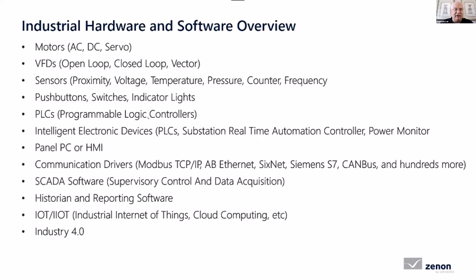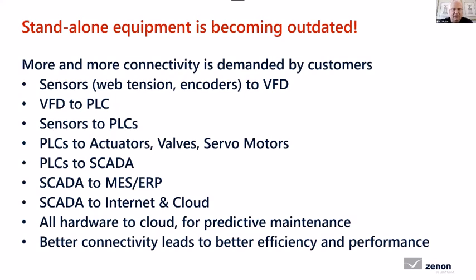Of course that's changing. Now people demand that equipment, hardware, and software all be interconnected, either to slightly higher or lower levels of equipment, or straight to the cloud. At home you might have a Nest thermostat that goes right to the cloud, whereas in a building you might have thermostats connected over a BACnet network, which goes to a Johnson Controls or Siemens system that operates dampers, chillers, heaters, and ventilation systems throughout the building.